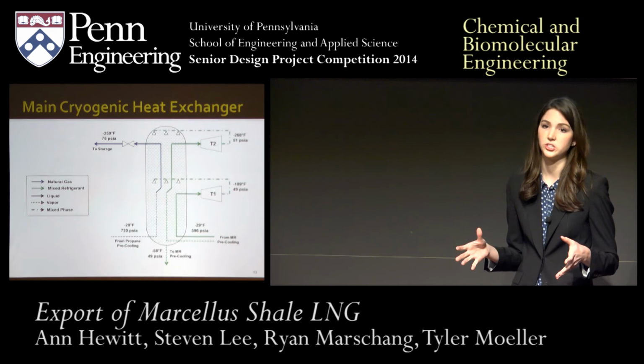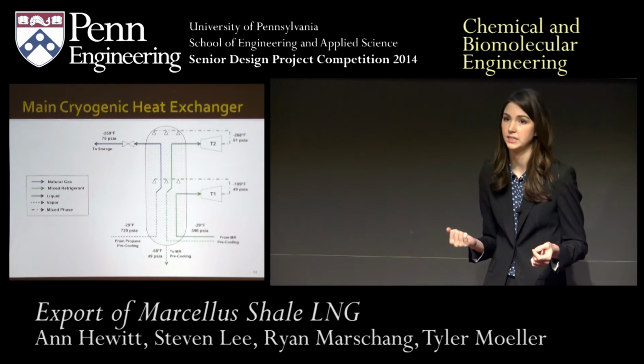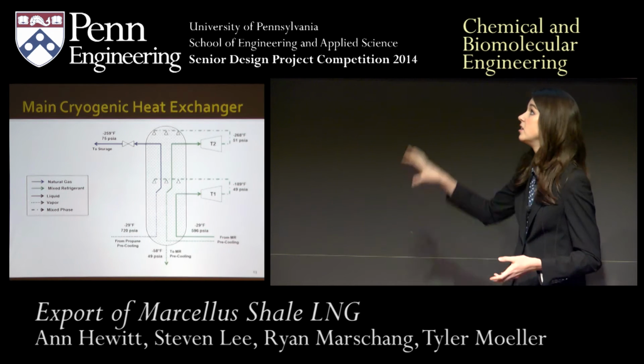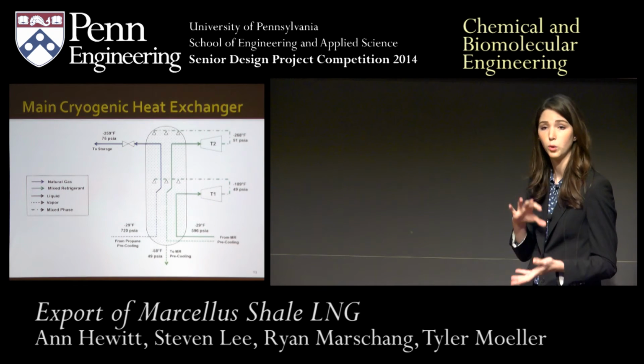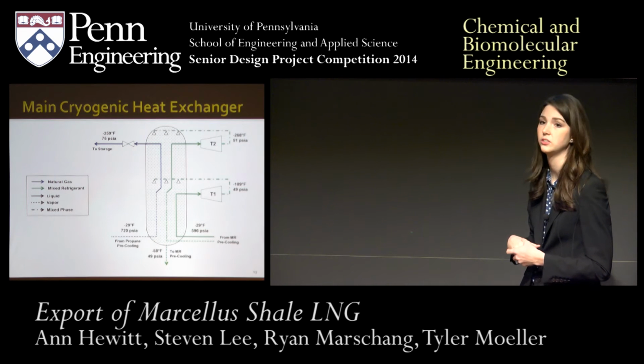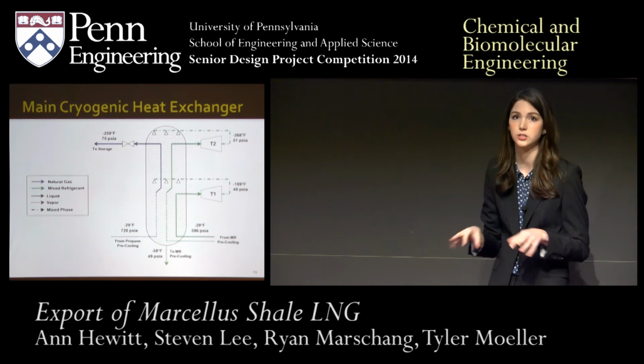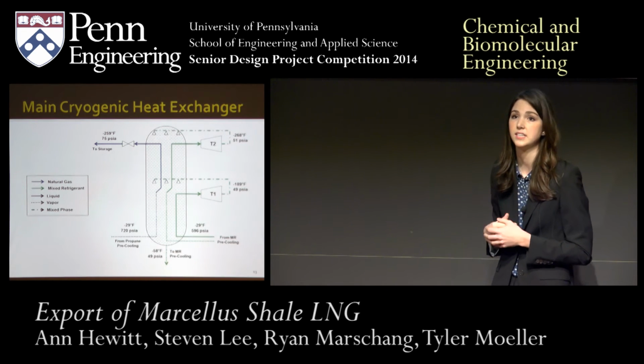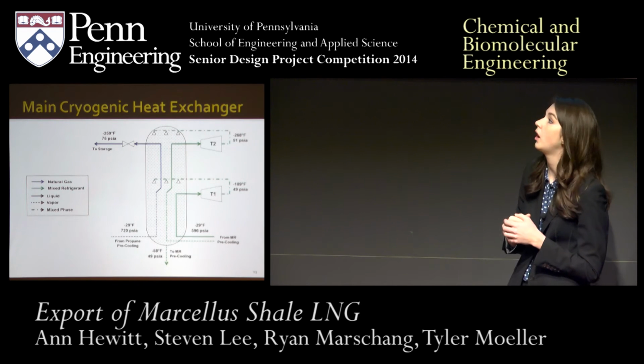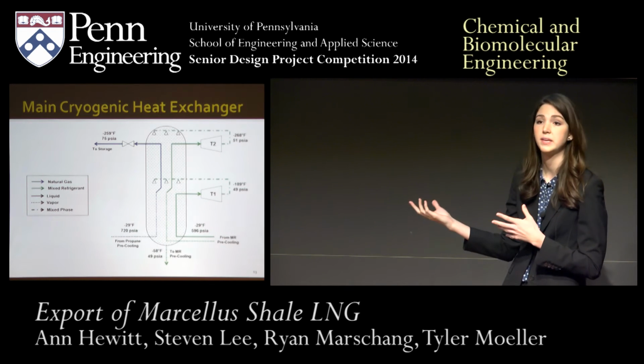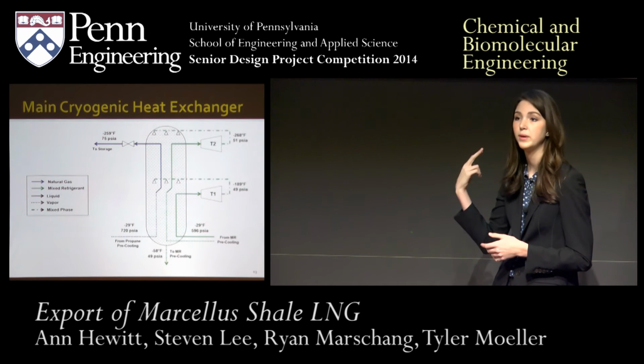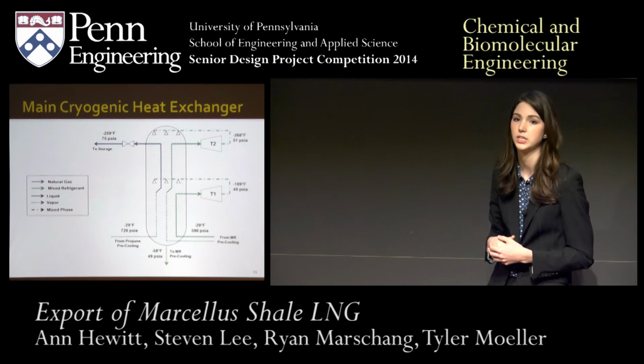The way this heat exchanger is set up is like two spiral wound heat exchangers in one vessel. In the bottom half, we have what we call the warm bundle, and in the top half, we have the cold bundle. We have three different streams entering through three separate tubes into this heat exchanger: in blue, our natural gas stream coming in from our propane pre-cooling, and then the two mixed refrigerant streams that I just mentioned.